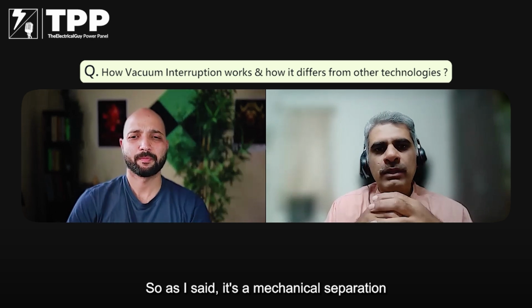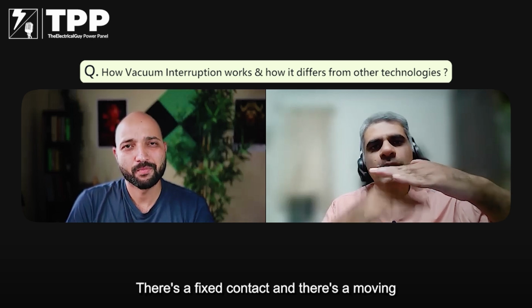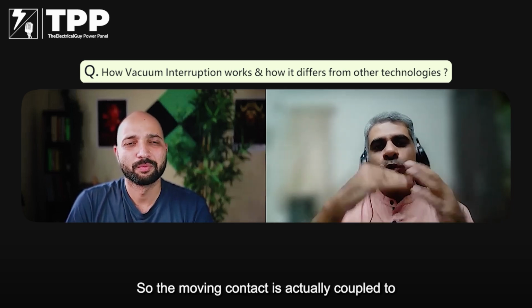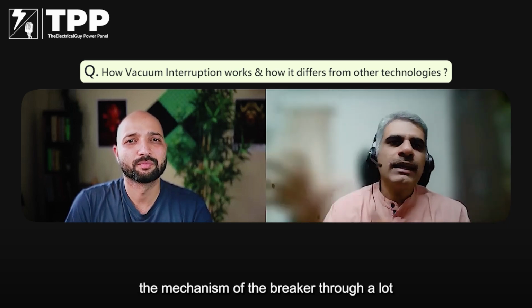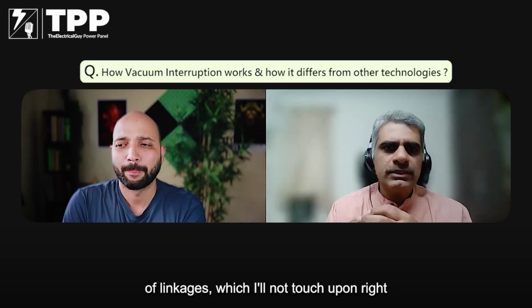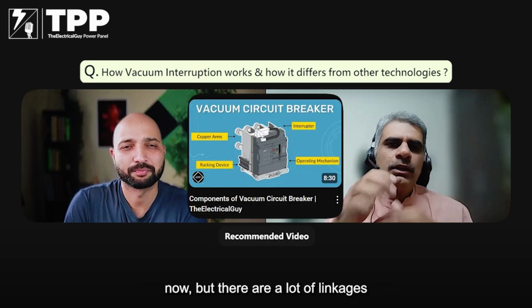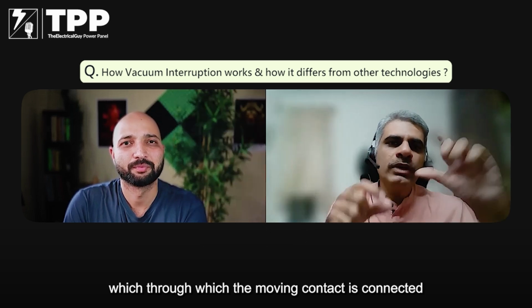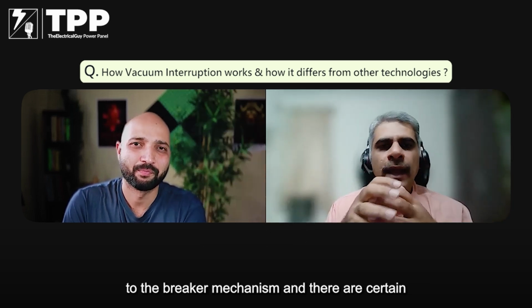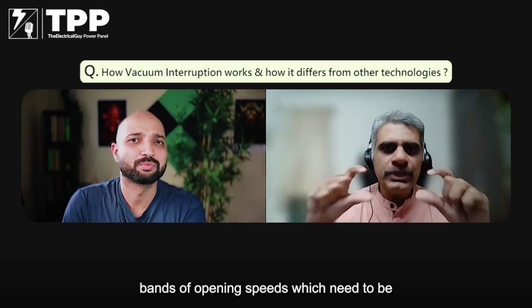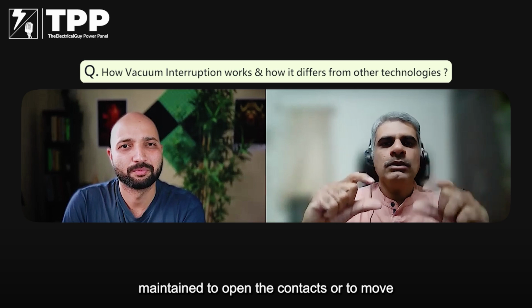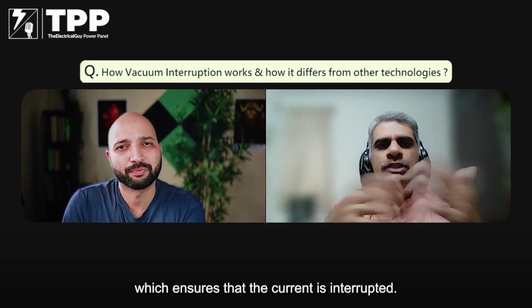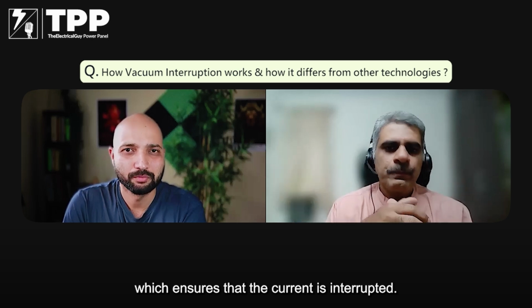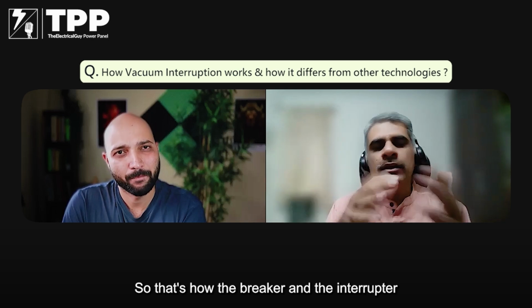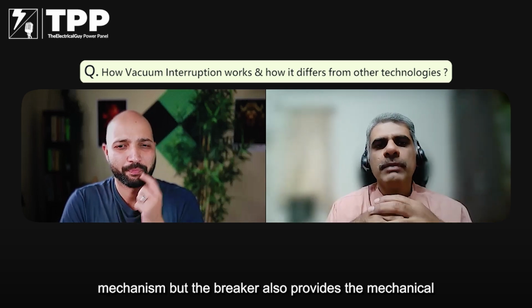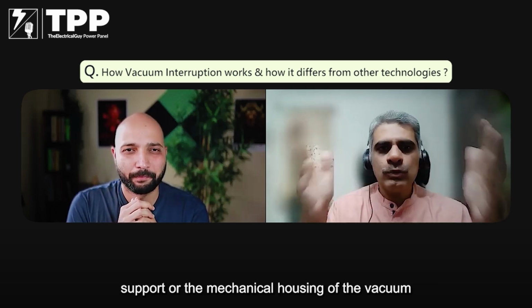As I said, a mechanical separation of contacts takes place. There's a fixed contact and a moving contact inside a vacuum interrupter. The moving contact is coupled to the mechanism of the breaker through a lot of linkages, which I'll not touch upon right now. There are certain bands of opening speeds which need to be maintained to move the moving contact away from the fixed contact, which ensures that the current is interrupted. That's how the breaker and the interrupter are coupled to each other. Not only the mechanism, but the breaker also provides the mechanical support or mechanical housing to the vacuum interrupter.